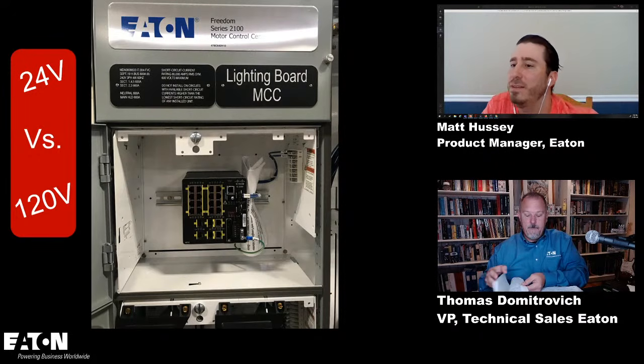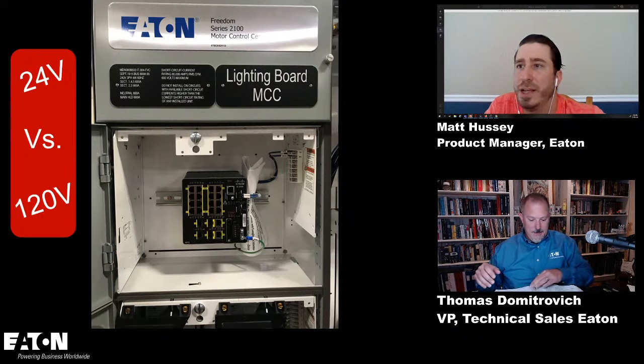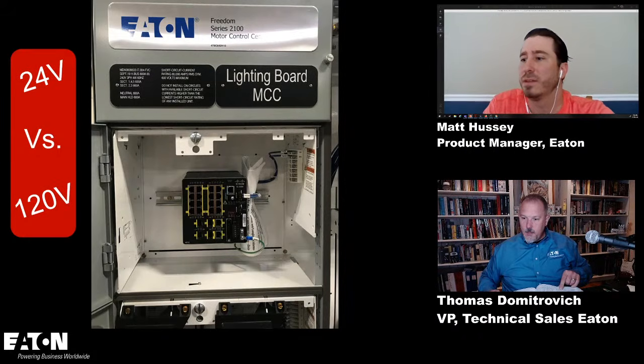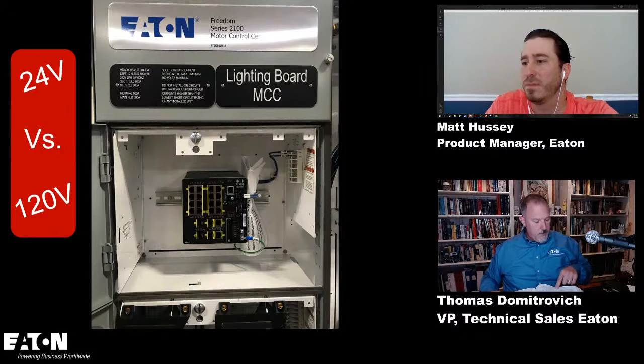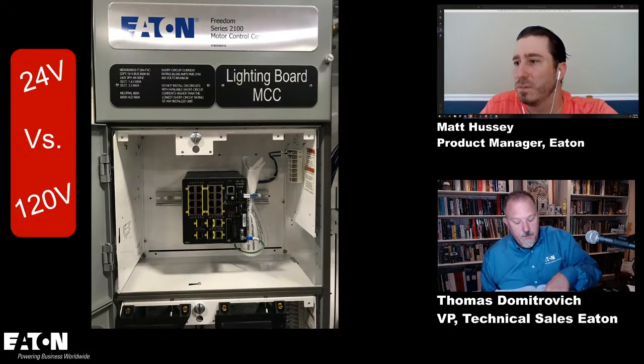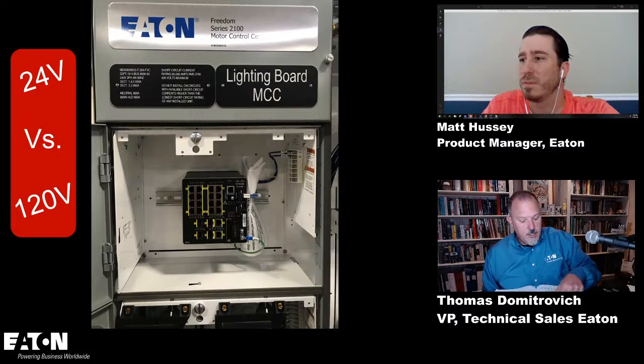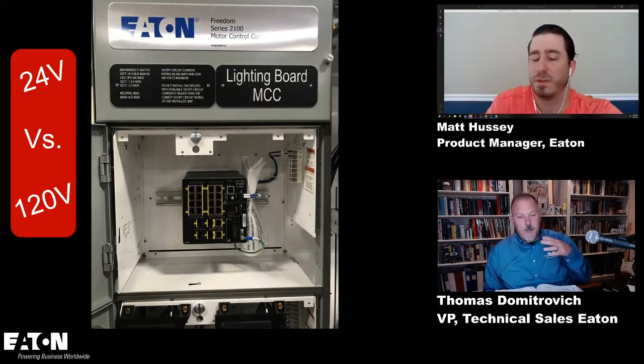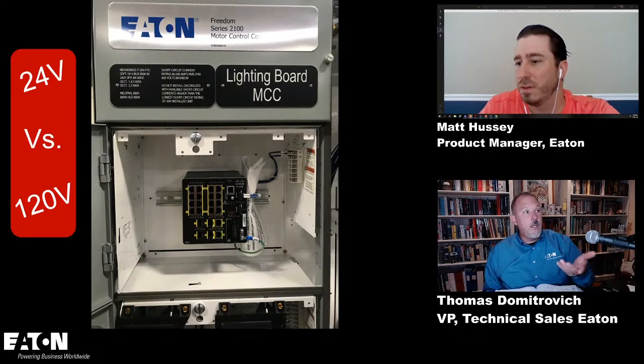I think that gets into the topic of power limited tray cable versus raceways within enclosures. 136(D) is in enclosures: Class 2 and Class 3 circuits shall be permitted to be installed in a raceway to separate from Class 1, non-power limited fire alarm and medium power network broadband communications. D is associated systems within enclosures. That's the one I think you're referencing. Class 2 and Class 3 circuit conductors in compartments, enclosures, device boxes. I'm not going to read through this right now, but I know when we had Incom and whatnot, we used the blue hose, which was 600 volt rated insulation.